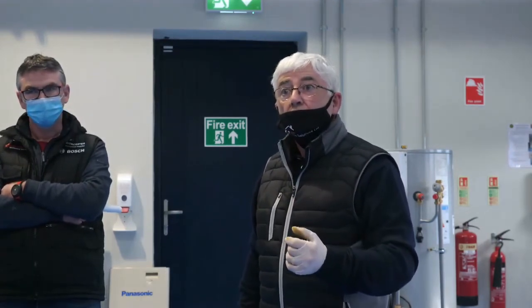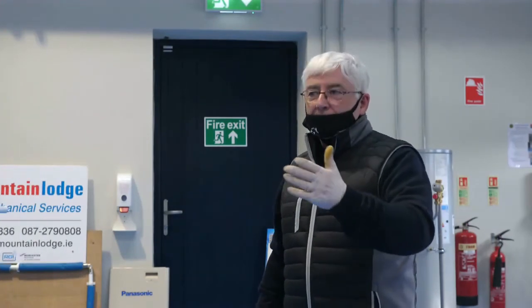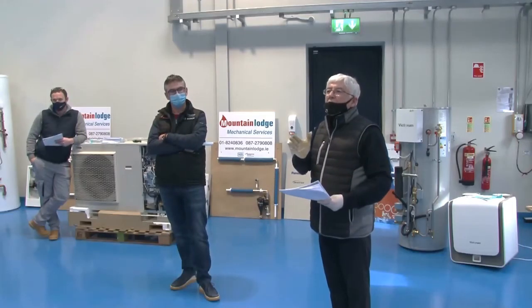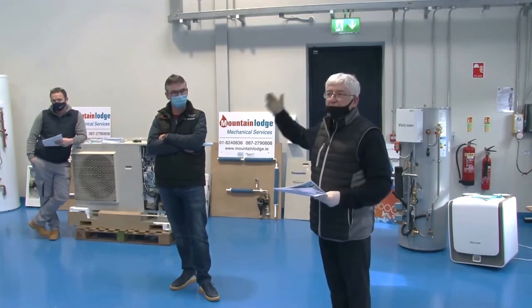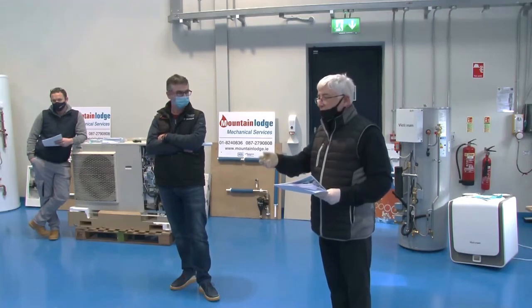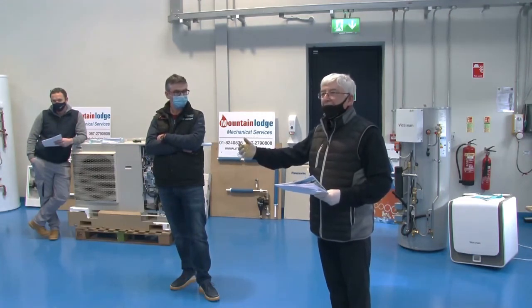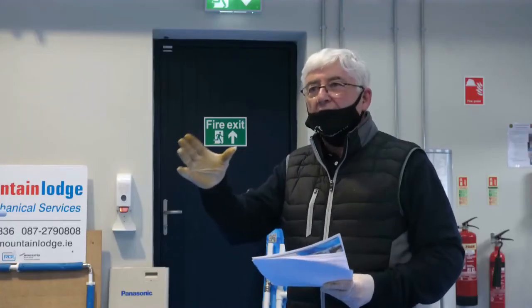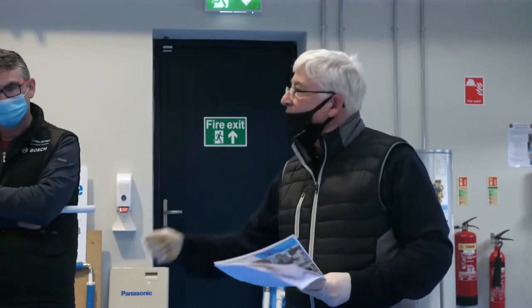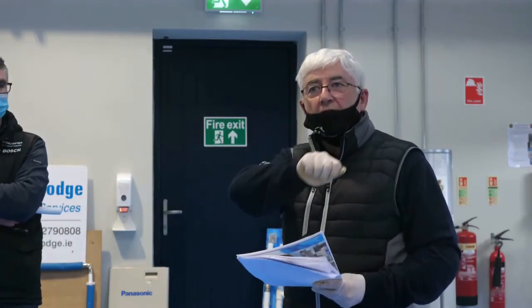And you're looking for the bar pressure on the pipe to correspond to, or be greater than, the one on the system. You're going to get maybe a 3-bar pipe or a 6-bar pipe or a 10-bar pipe. I can buy a 3-bar pipe cheaper than a 10-bar, so you have to watch that somebody's not using the cheapest product they can without really making sure it's fit for purpose.